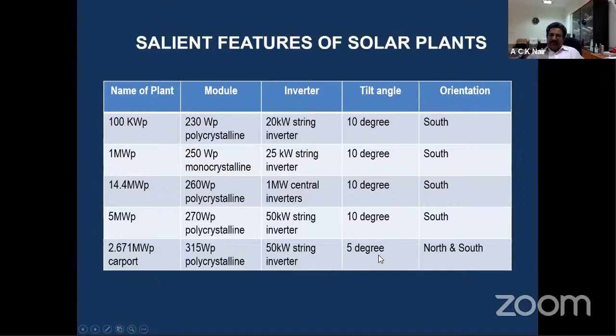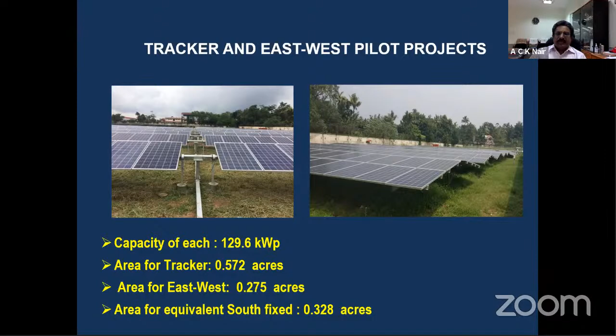The 2.671 has 315 watt polycrystalline panels, with a 5 degree tilt towards both north and south. We also installed a tracker system for a sample study. The capacity was only 129.6 kilowatt, and the area of the tracker is 0.572 acres, and the area for east and west is 0.275 acres. So the area for the equivalent south fixed is 0.328 acres. The gain was not much compared to the cost we incur for having the tracking system. It is not much of an advantage, so we have not gone further into that.